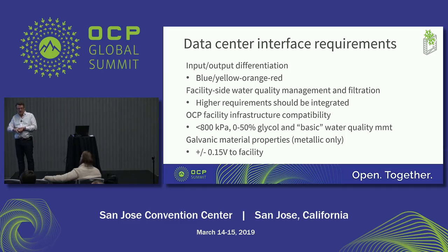I got the question, why not 55%? This comes from some of the experience that I've had myself with developing immersion technology. Some controllable valves that actually function properly have an upper limit of 50% glycol. Beyond that, they may risk getting stuck, or sensors may stop giving reliable readings. So it's based on experience that some of the intricate features that you want to be able to build into immersion solutions may actually be affected with glycol percentages beyond 50%.